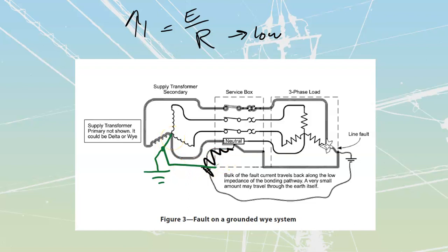So if I follow my path through over here, if I have a fault on the system, it's going to travel all the way through. Once it hits here, we can either send some along to the earth, but the bulk of it is going to go along my bonded path back up to the transformer itself, where once again, we are going to complete that path across here. That's going to be for a Y type of system.